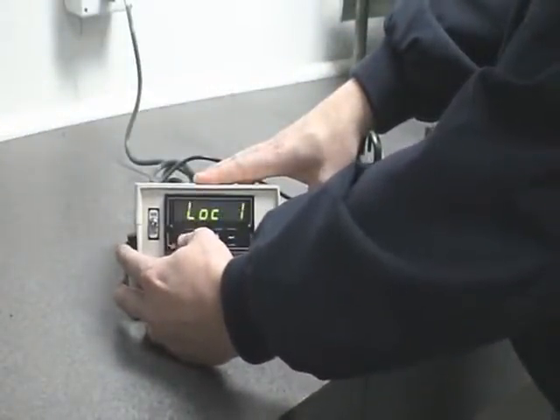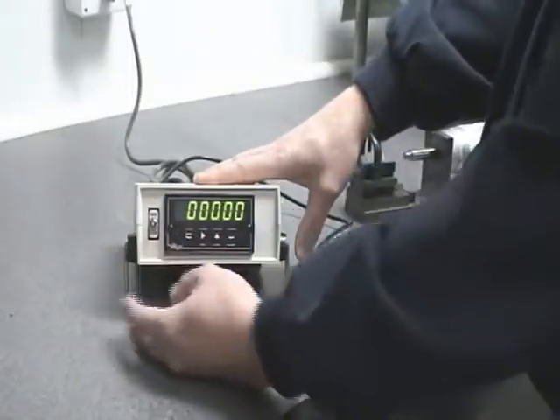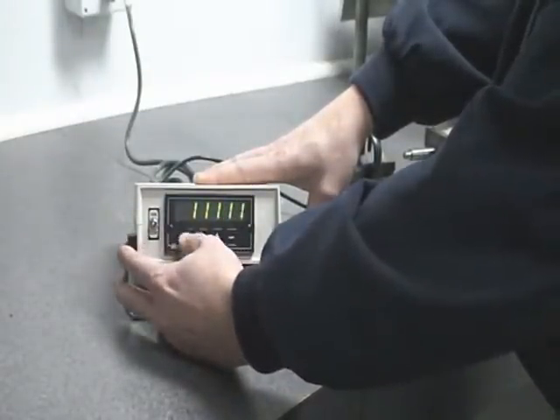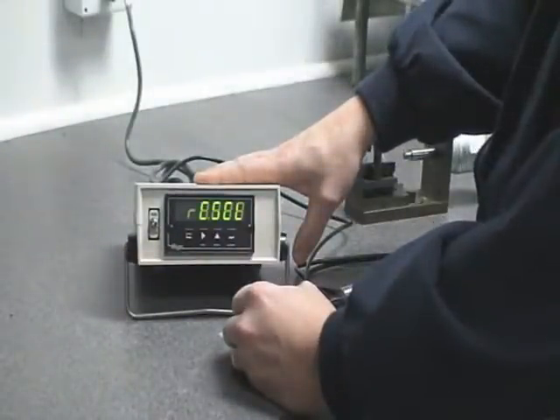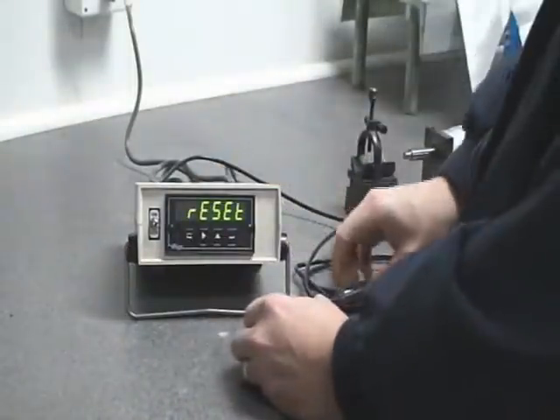Once you've finished calibrating your device, you can lock out your meter. Go to lock one, hit the peak button and change each number to one. For the standard E405, that's the only lock you would have to worry about. The meter is reset and nobody can mess with your readings.